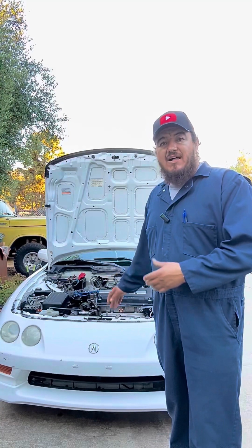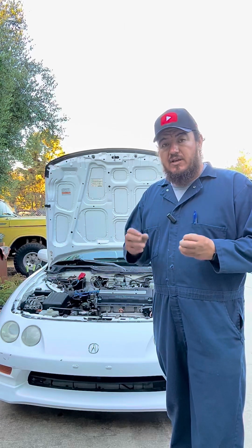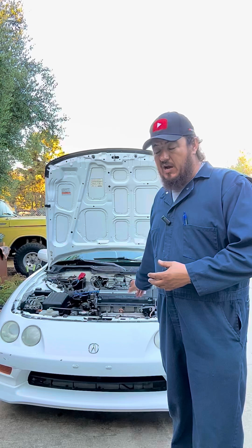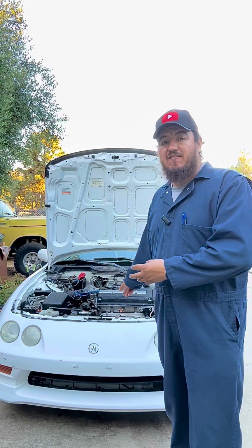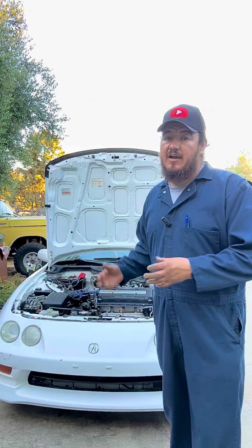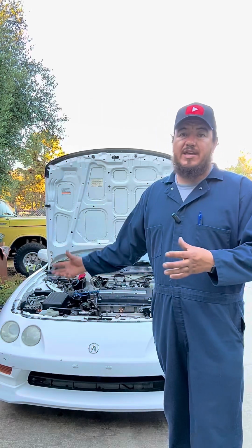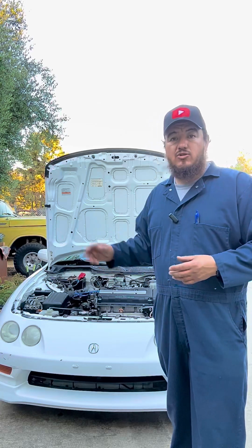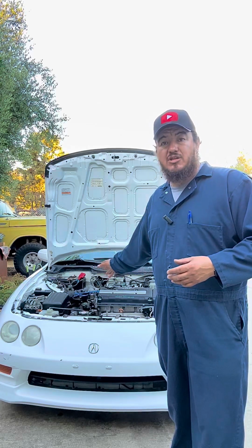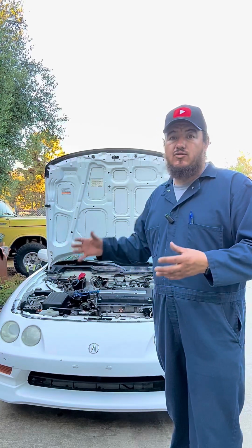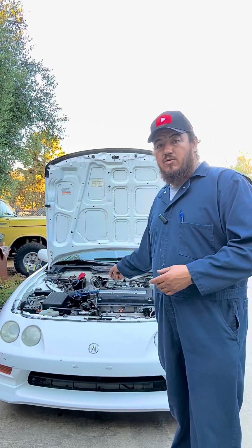Now that we know that valve is a problem where the gas or freon is being lost slowly, to open or replace the valve we need to evacuate the system properly. That requires a cylinder and other equipment so we can evacuate and have the system ready to be opened, because right now it's under pressure and there's so much freon in there that we can't just let it off into the atmosphere. So we need to recover it properly so we can work on the system.